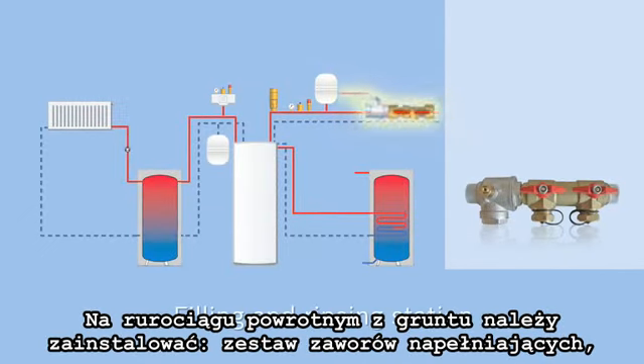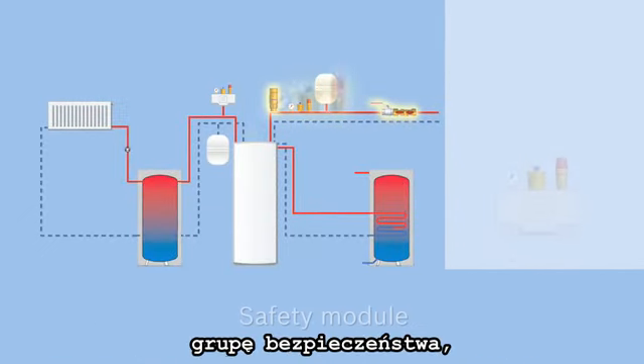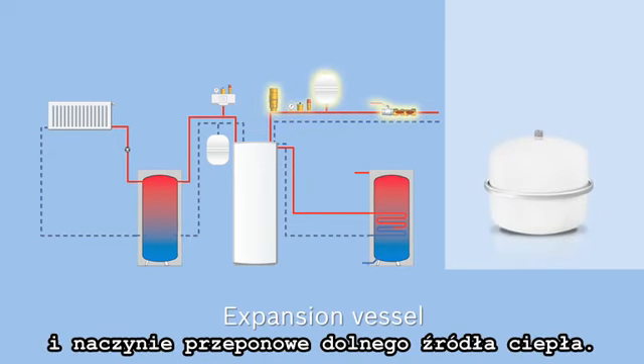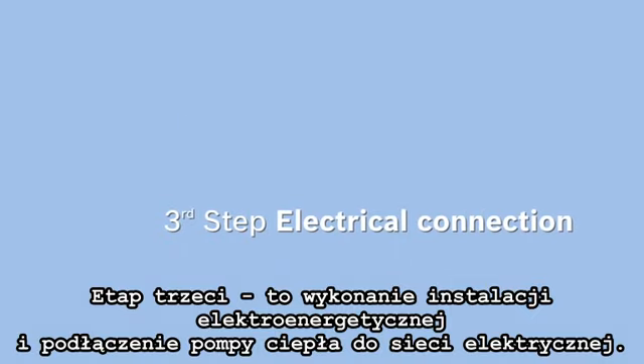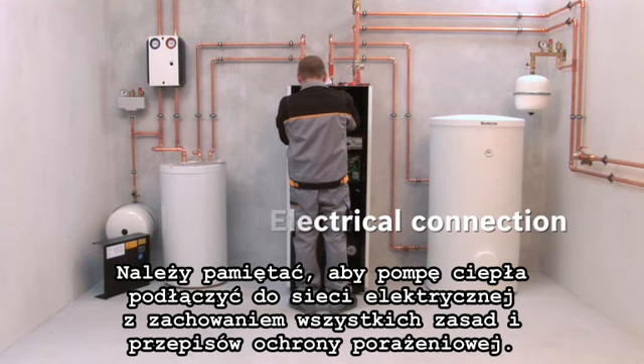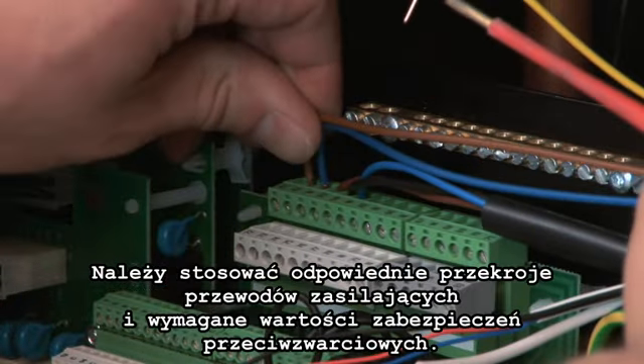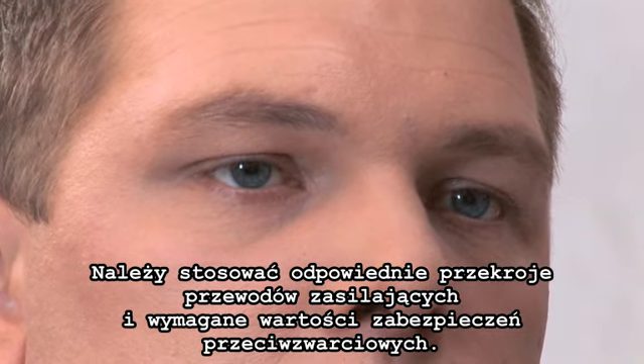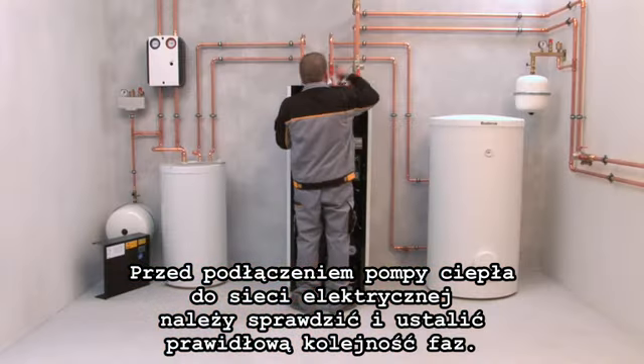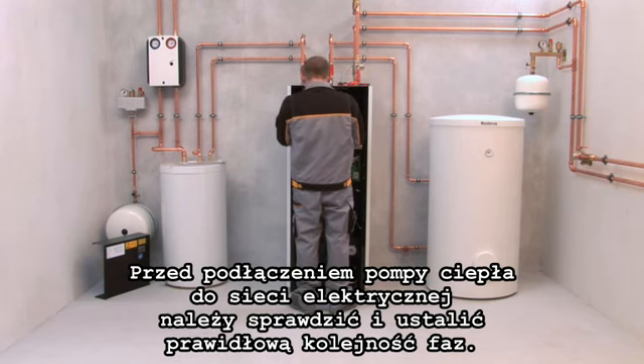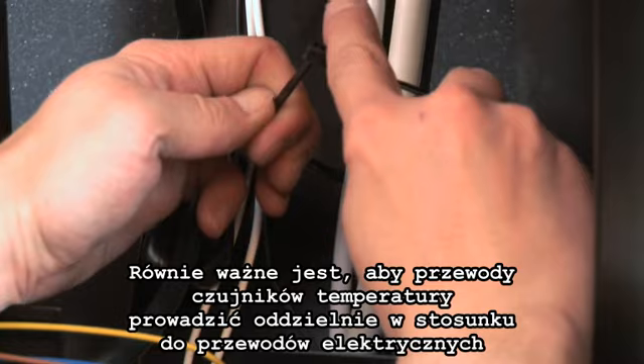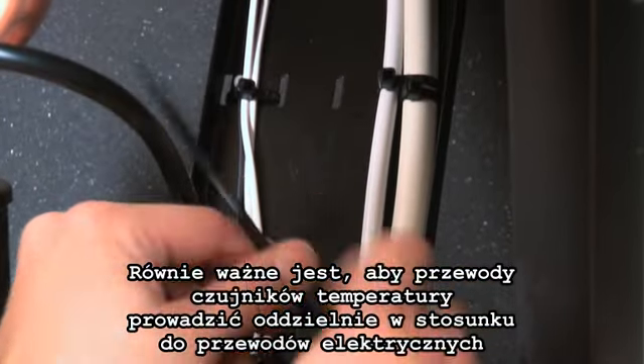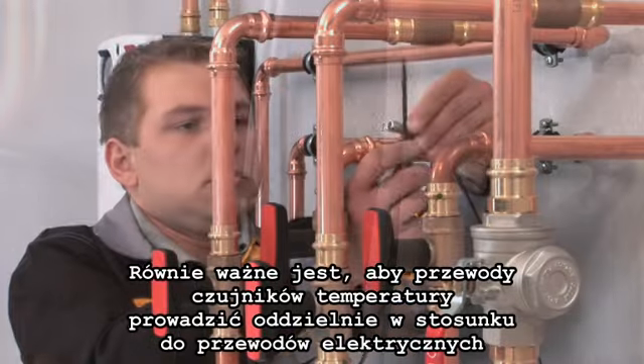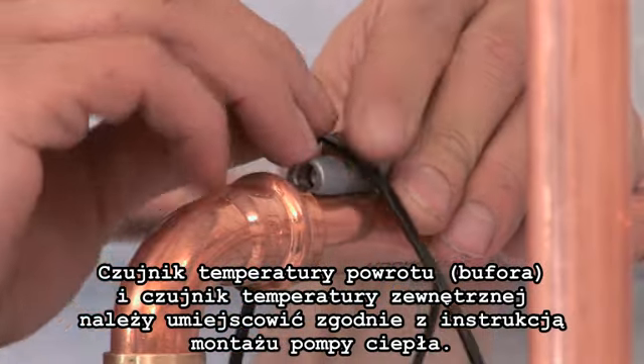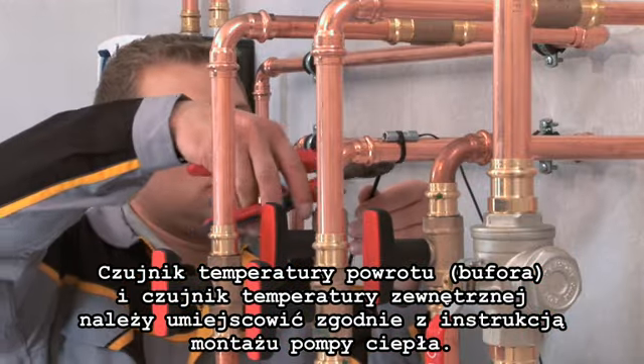Now install the filling and rinsing station, the large breather, the safety module and the brine expansion vessel. In order to complete the installation, an electrician installs the corresponding connections. For this purpose, the integrated electric consumers of the heat pump are connected according to the standards of the energy supply company. Before supplying power to the system, please check whether the phase sequence was set correctly. In addition, it is important to lay the sensor lines separated from the current carrying wiring. The reflux sensor has to be connected according to the manufacturer's installation instructions.